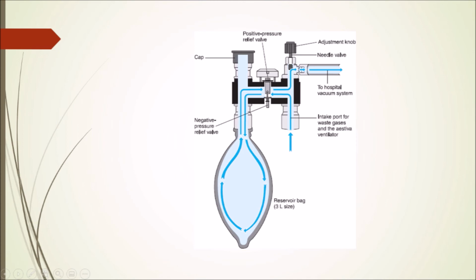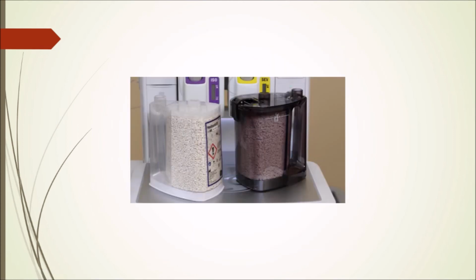The typical anesthesia machine absorber is a clear plastic canister or collection of canisters of varying sizes, but at least of the same volume as the patient's typical tidal volume. The canister is full of some type of alkali absorbing granules. The canisters are incorporated into the ventilatory apparatus of the anesthesia machine between the expiratory and inspiratory limbs of a circle circuit.